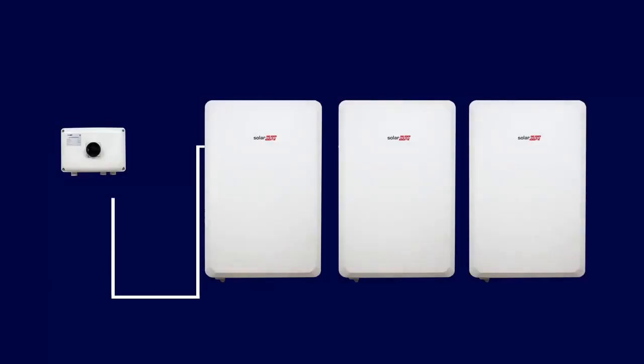If only two SolarEdge batteries have been connected, these can be wired directly to the inverter. If however three SolarEdge home batteries are being used, you'll need to use the DC combiner.